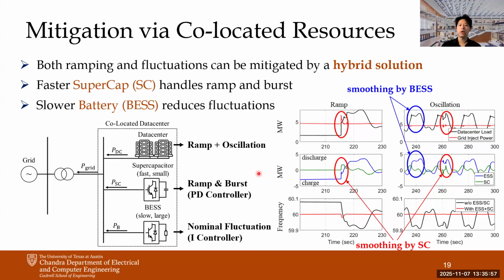So based on this kind of co-located data centers, we can minimize the fluctuation as well as the ramping, like this right figure. In the case of the ramping event or the very instantaneous large deviations, the supercapacitors take a large part of the smoothing, and in the case of nominal deviations, BESS can do their work. In the frequency, you can compare that the red lines, based on power smoothing from the co-located resources, have much smaller deviations than the baseline cases in the black lines.